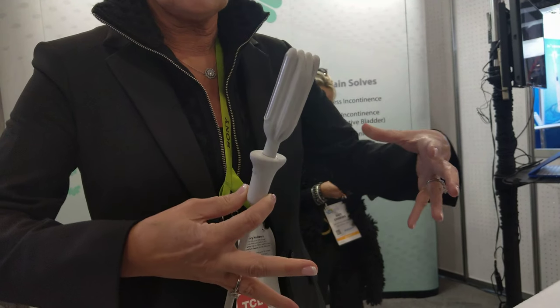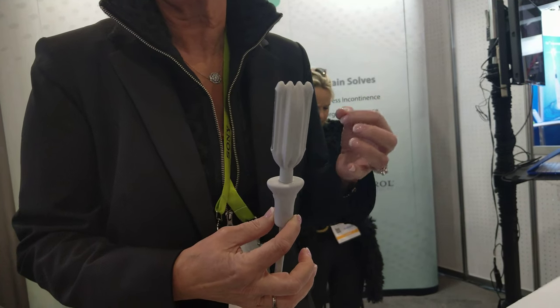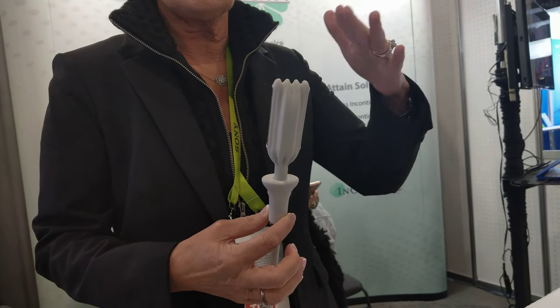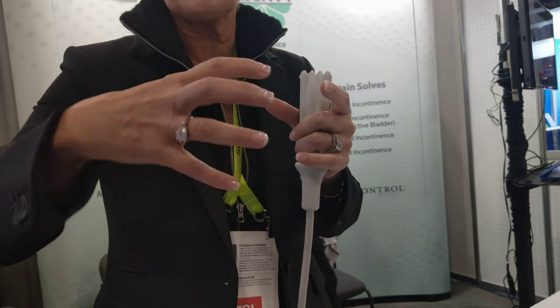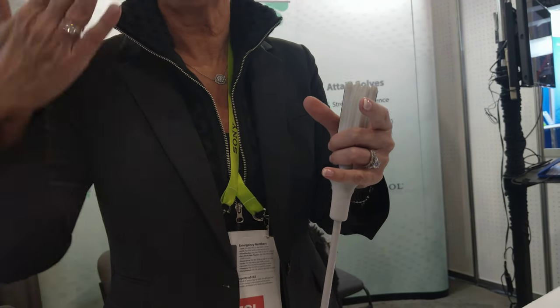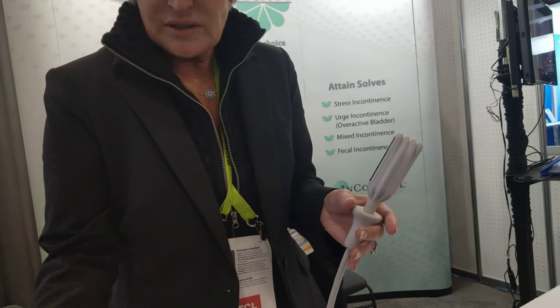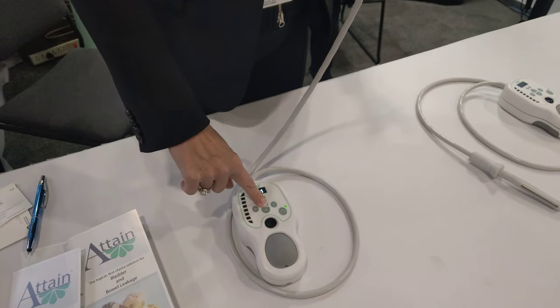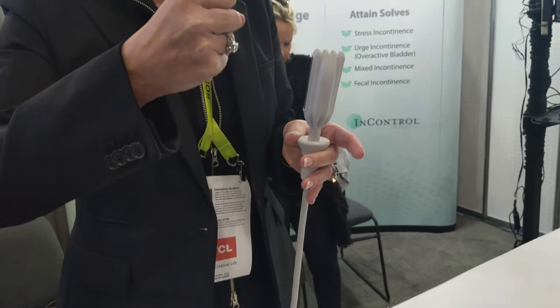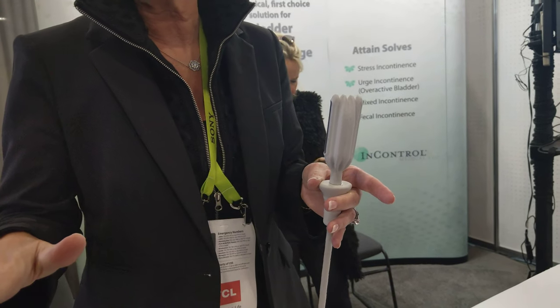The end user contracts their pelvic floor muscles, strengthening them better and more efficiently than they can do on their own. It also alternates with a calming sequence — we calm the muscles surrounding the bladder because that's what's spasming and causing that urgency and frequency. They deliver muscle stimulation and once they feel a nice contraction and relaxation around the probe, they let the device do the work.